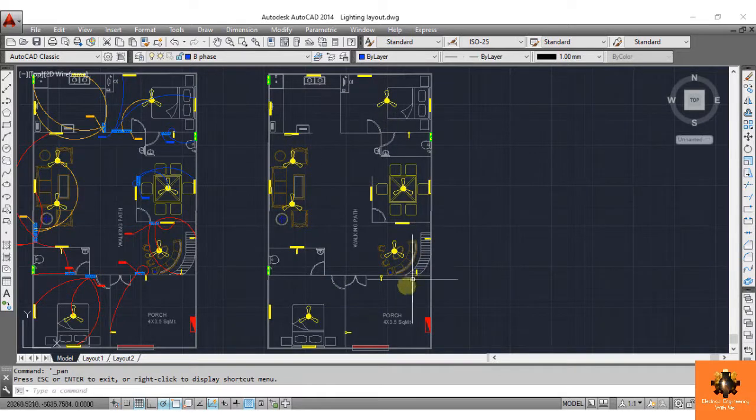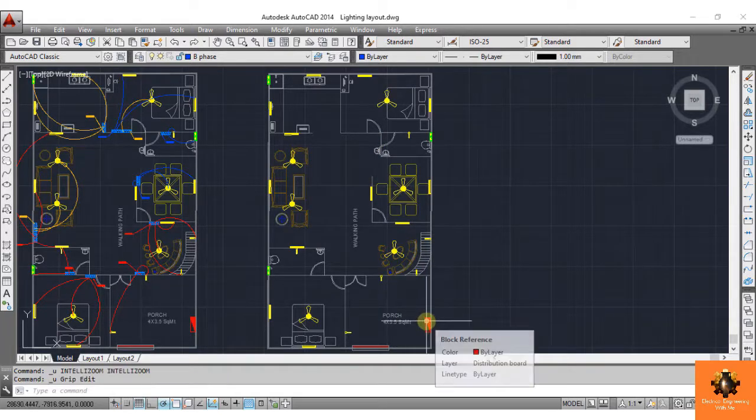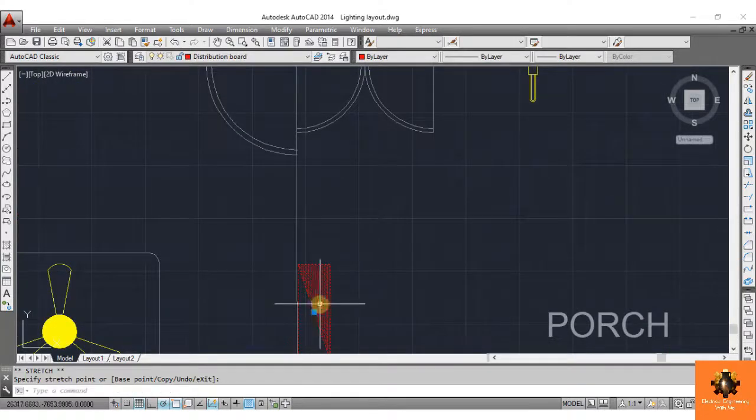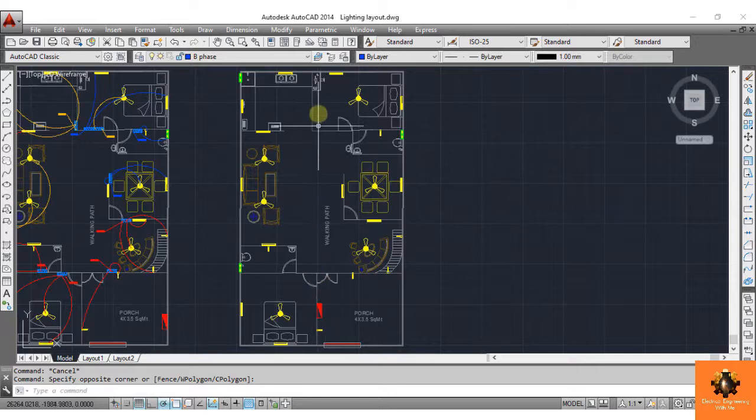Here we have placed all the fixtures, meaning fluorescent lamps, CFL, ceiling fans, exhaust fans and all. Now note one point. In this plan we are taking one main conduit that will go from the front side of the building to the end of the building. From this main conduit, we will take branches and sub branches to interconnect all these fixtures. So draw the main branch from this DB. But for simplicity, I am moving this DB to this wall, because now I can draw the main branch in the middle of this ceiling. Okay, so draw the branch.